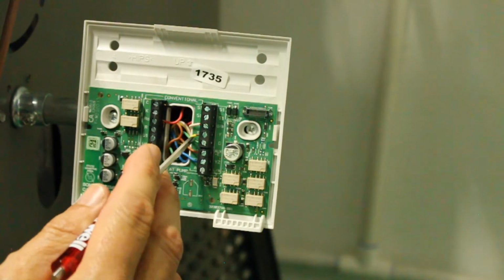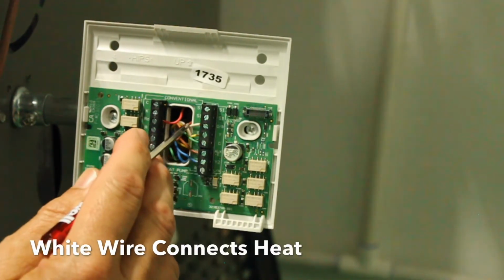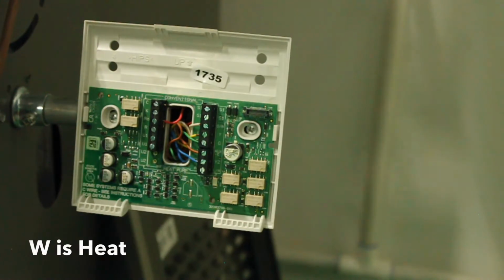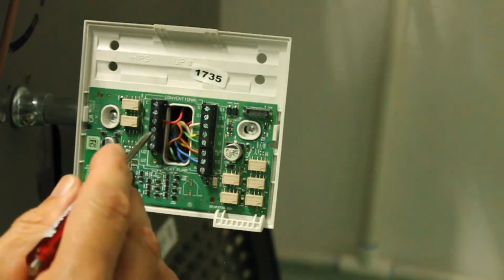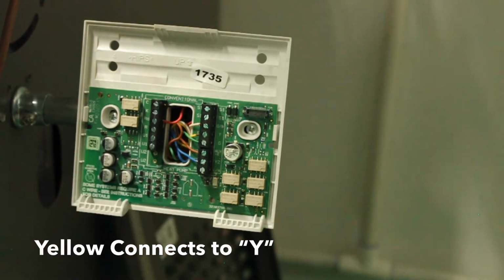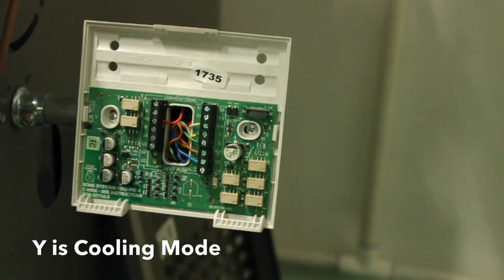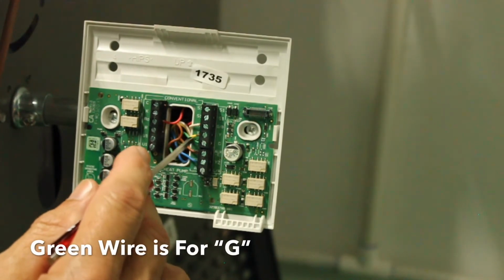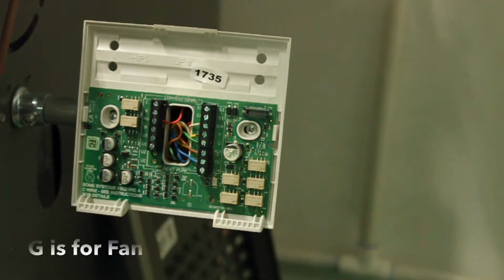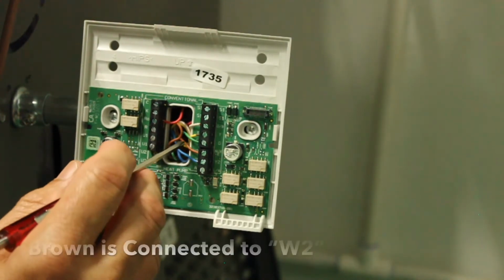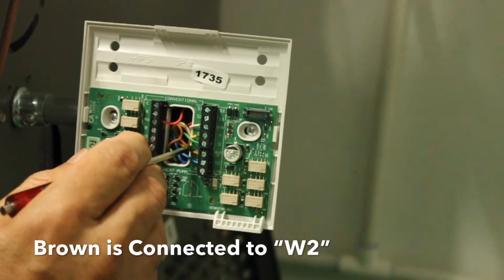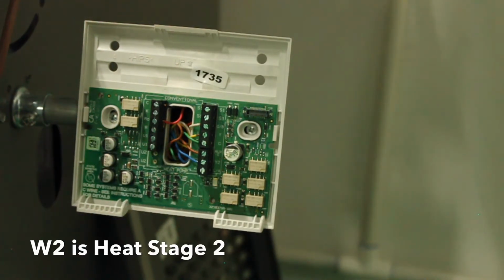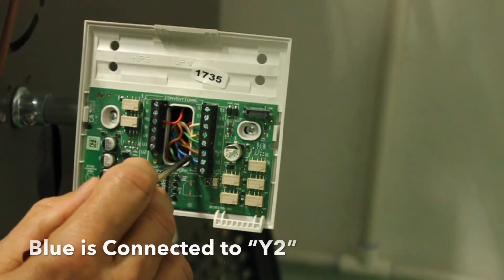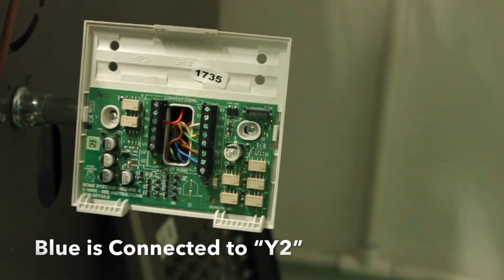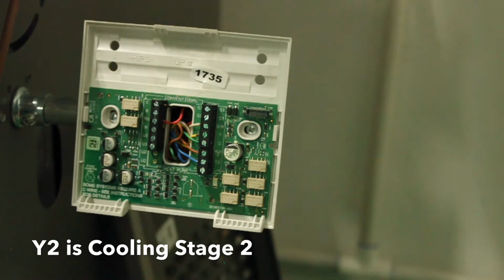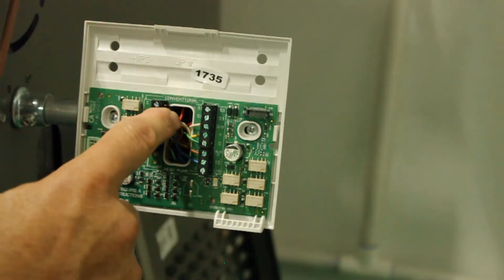Then on the other side, let's take a look at these 5 wires. They use the white wire to connect to the heat. W is heat, so they connect it to the W. They use the yellow wire to connect to Y, which is the cooling mode. And then the green wire is for G, which is for fan. And we're looking at the brown wire, and they're connecting the brown wire to W2, which means heat stage 2. And the blue wire is connected to the Y2 terminal, which is your cooling stage 2. So very important to know which wire goes where.